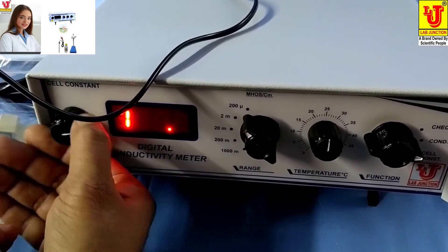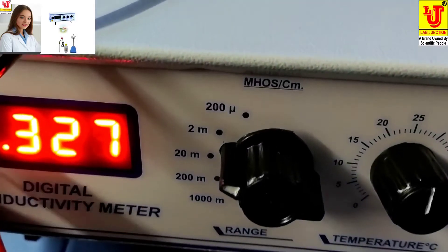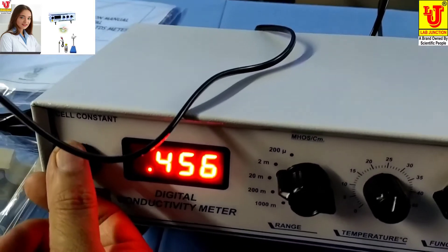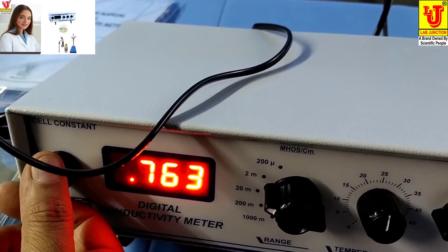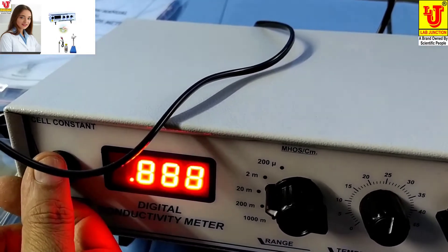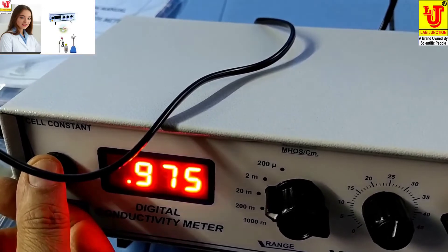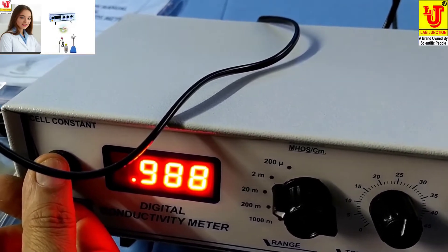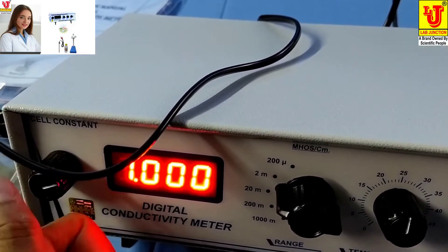This is our range on the first position. Now you can set it to the second range and adjust it to your standard solution value of 1 millisiemens. Now your digital conductivity meter is calibrated and ready for use.